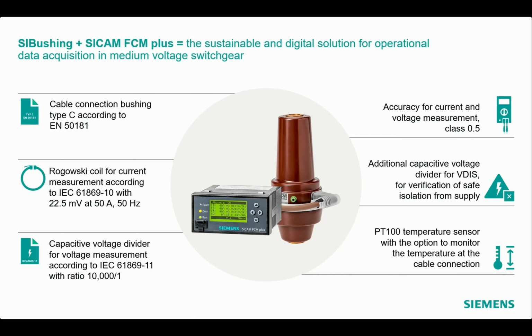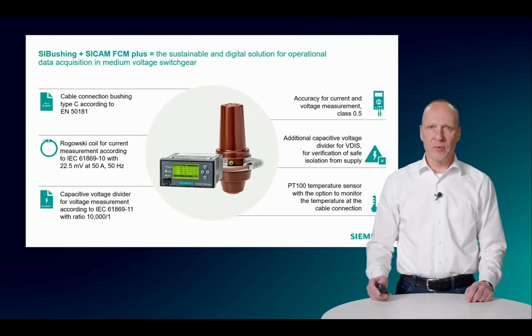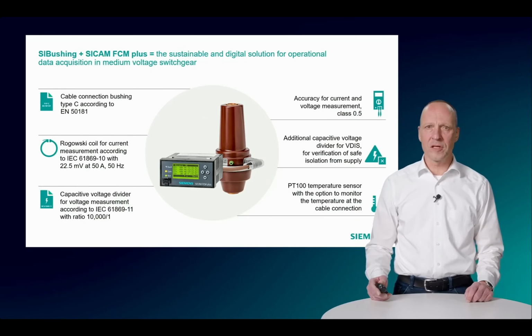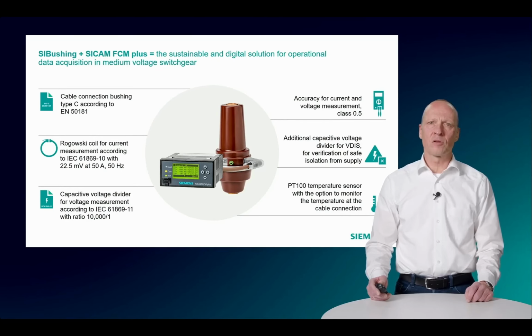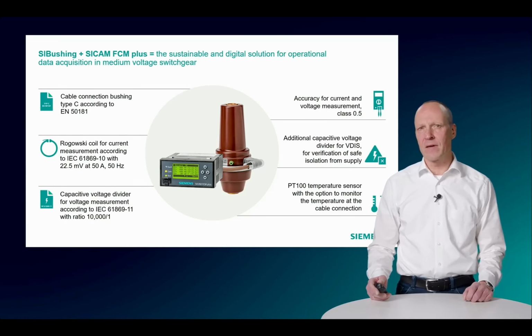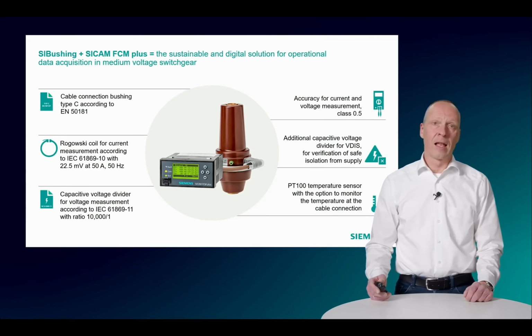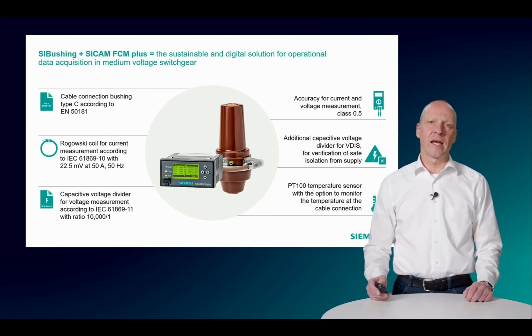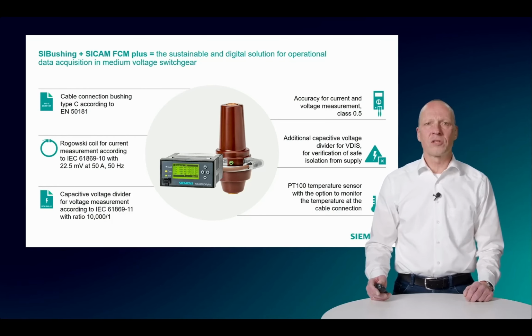We have integrated an additional temperature sensor, which is used for compensating the voltage accuracy over the whole temperature range from -40 degrees to +115 degrees. This temperature sensor can also be used for further supervision of the cable connection and also to provide the temperature information via the short circuit indicator and the gateway into Electrification X for further use in different feature sets. Last but not least, we have the standard VDIS voltage divider integrated, which is used for verification of the absence or presence of the voltage.